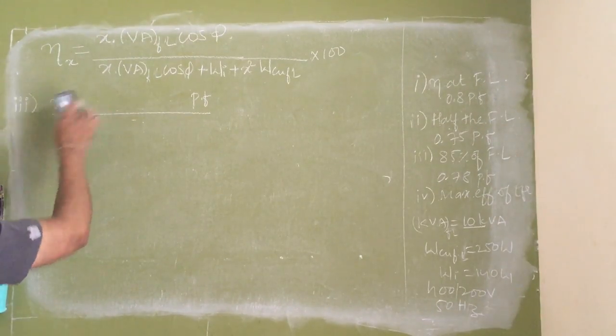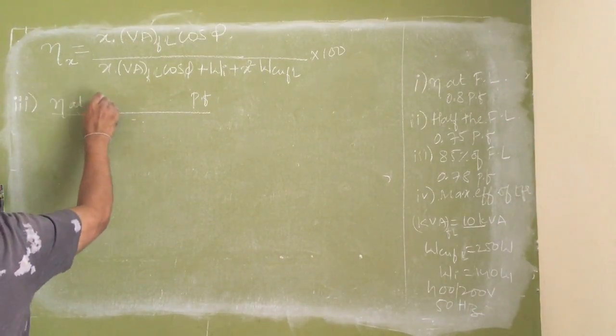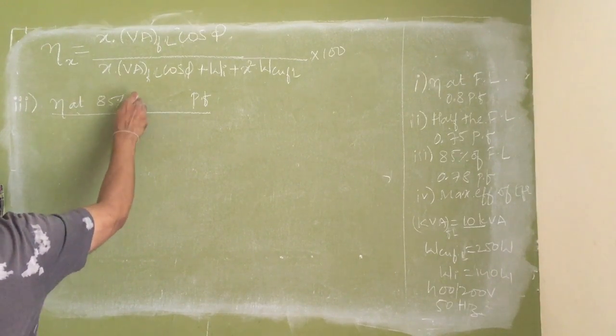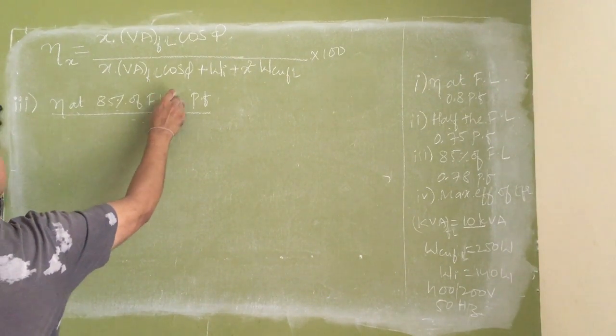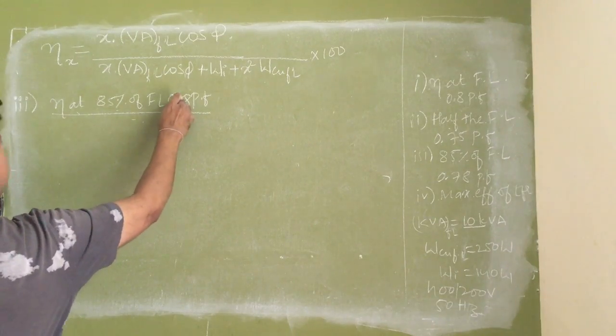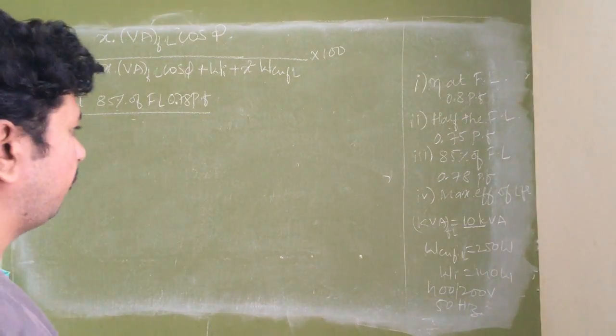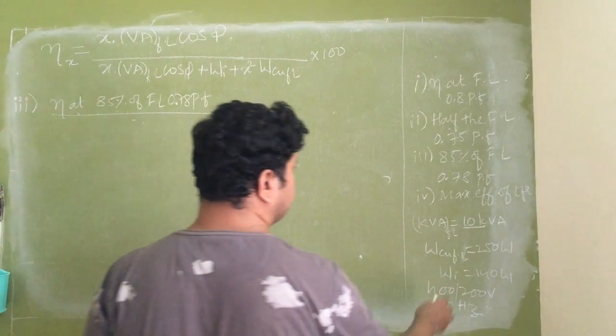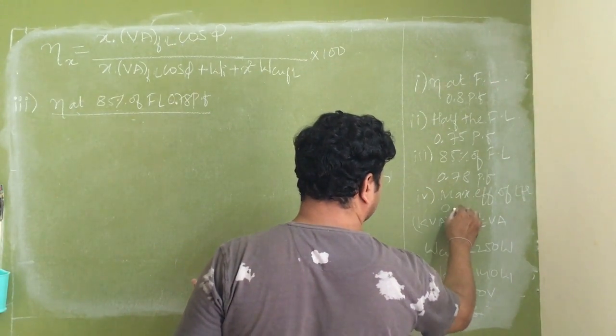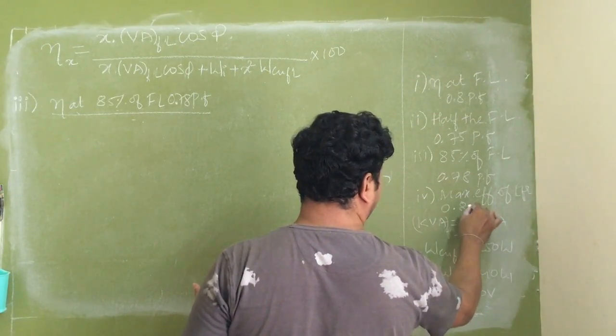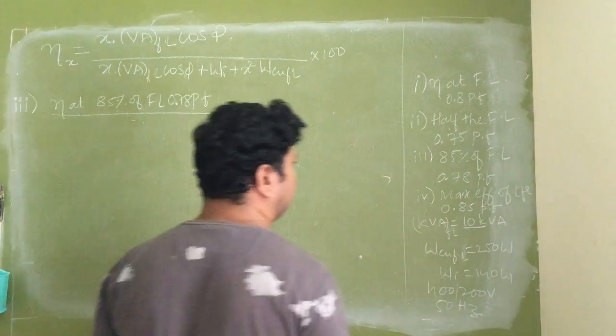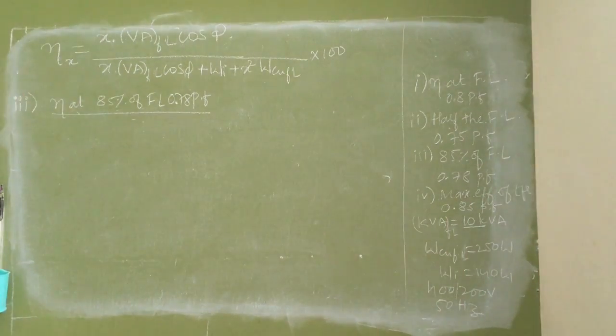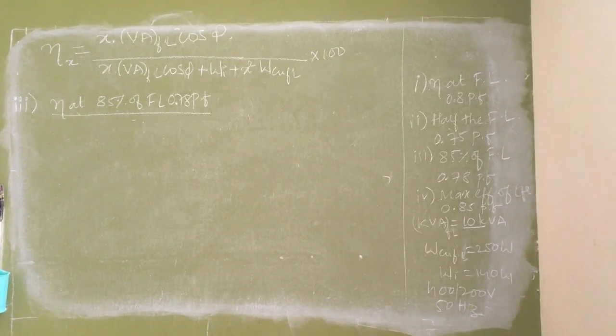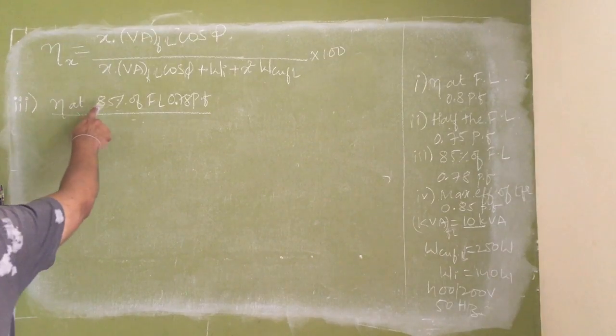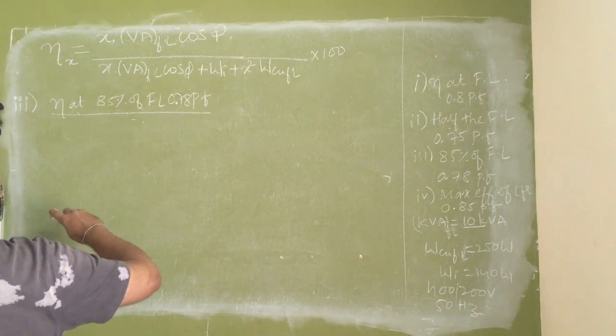Case 3, efficiency at 85% of full load, 0.78 power factor. Maximum efficiency of transformer at 0.85 power factor. We need power factor also. You please note that. Okay, so efficiency at 85% of full load, 0.78 power factor.